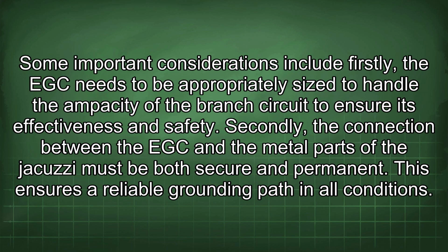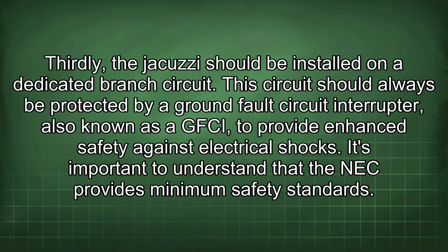Some important considerations include: firstly, the EGC needs to be appropriately sized to handle the ampacity of the branch circuit to ensure its effectiveness and safety. Secondly, the connection between the EGC and the metal parts of the jacuzzi must be both secure and permanent. This ensures a reliable grounding path in all conditions. Thirdly, the jacuzzi should be installed on a dedicated branch circuit.